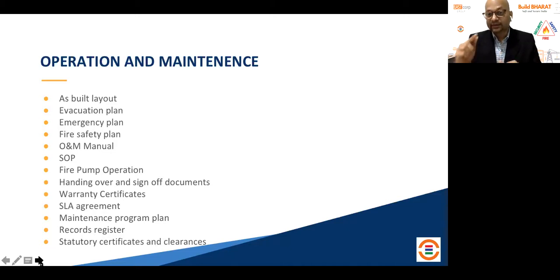But if the audit review has been done, then they know that the isolation valve, if at all you're going to use it on a sprinkler system, must be supervised. How do you supervise? Get the tamper switch connected to a fire alarm panel. Put the fire alarm panel in auto and functional mode. Know the exact location - if the person is going to switch off the isolation valve, you get an indication, you get a trouble signal. This is what your audit and review program does.